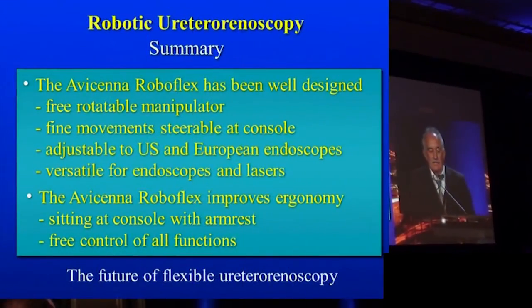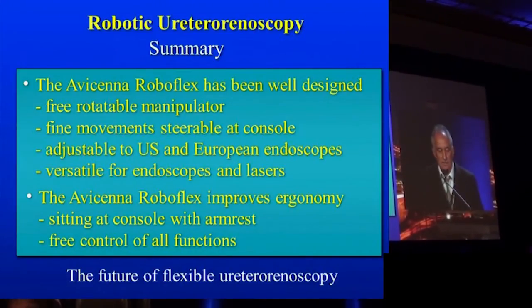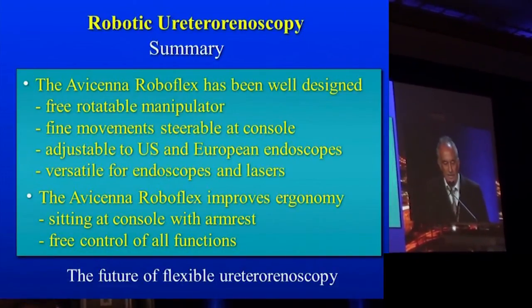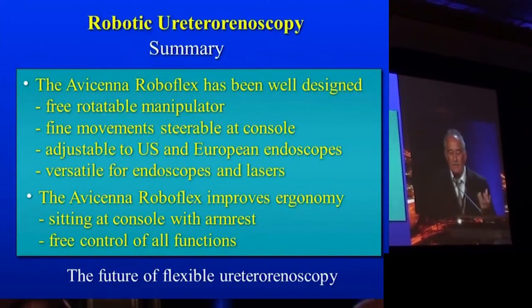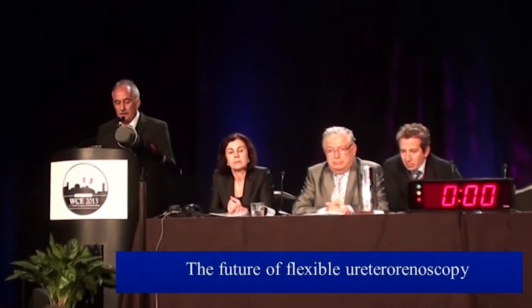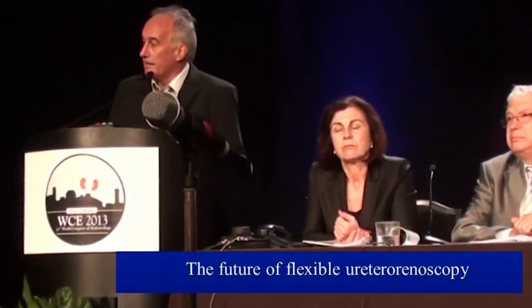In summary, the Avicenna Roboflex is a very well designed instrument — a freely rotatable manipulator with fine movement, steerable at the console, adjustable to US and European endoscopes, and versatile for endoscopes and lasers. The Avicenna Roboflex significantly improves ergonomics, allowing the surgeon to sit at the console with arms free and full control of all functions. In this view, it is truly the future of flexible ureteroscopy.